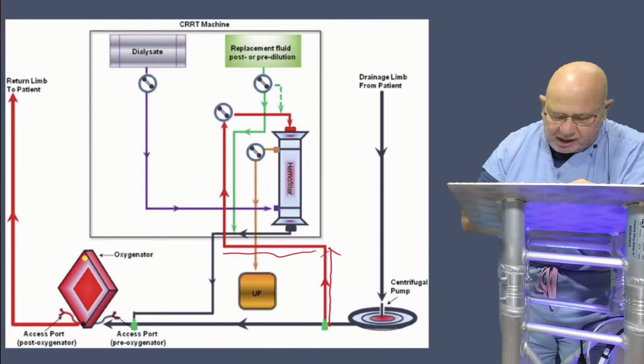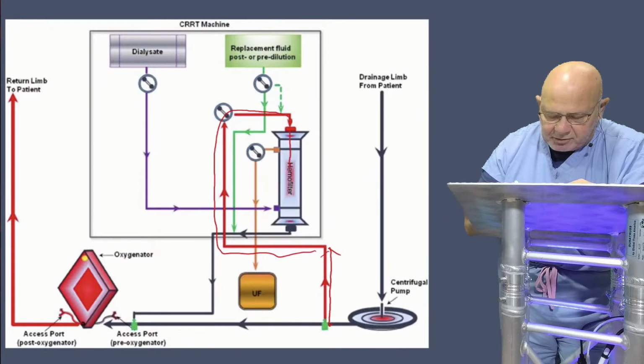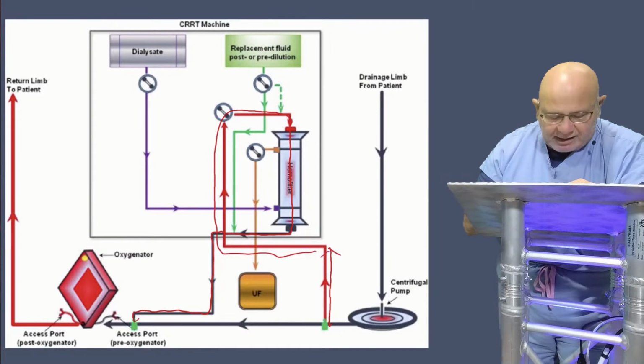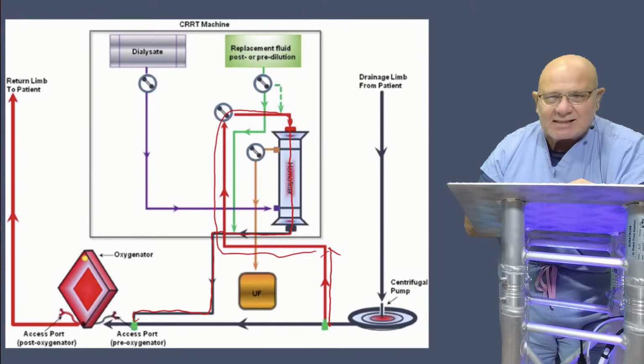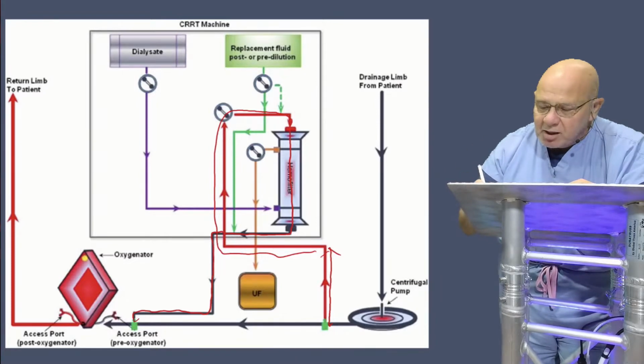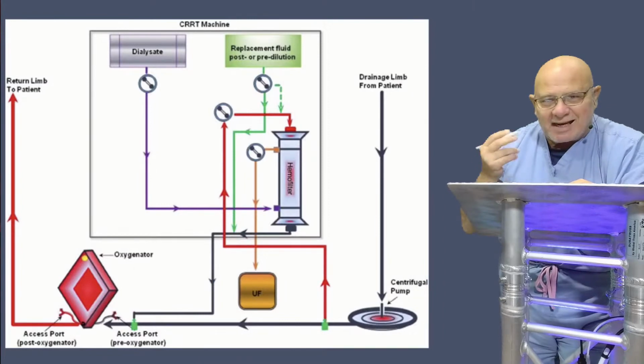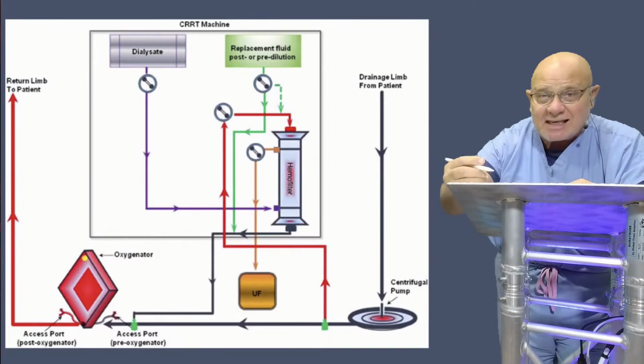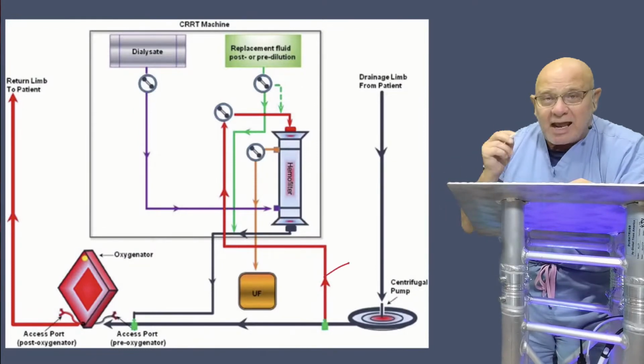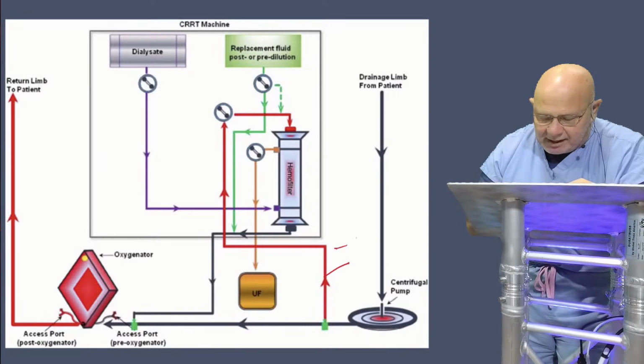And they're bringing it around, just follow it around, and they're coming in to the hemofilter, through the hemofilter, now down the blue line, which represents the darker blood, and it's coming in that line distal, but again, where the highest point of resistance in this circuit is. So if you remember what we talked about, the normal pressure that a CRRT machine expects to see in this arm, your access line, is a negative number, negative 50 to negative 150. But what it's going to see here is probably going to be, depending on flow and a variety of things, positive about 200 to positive 250.